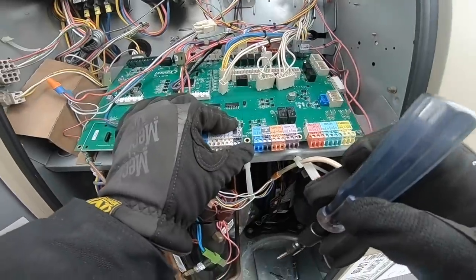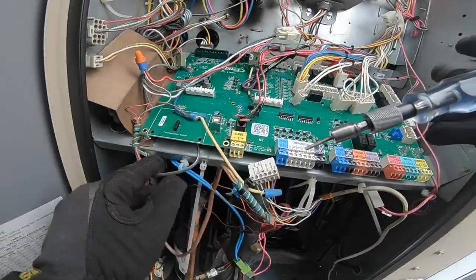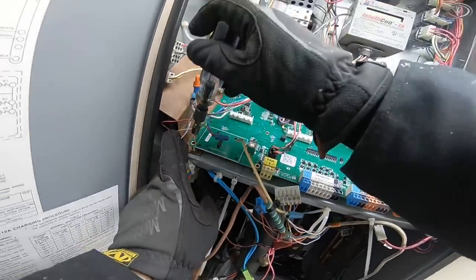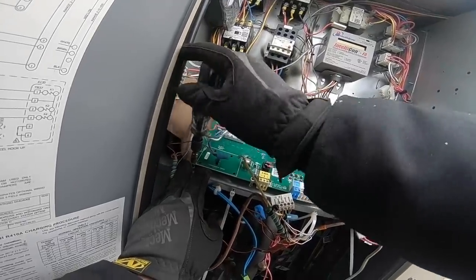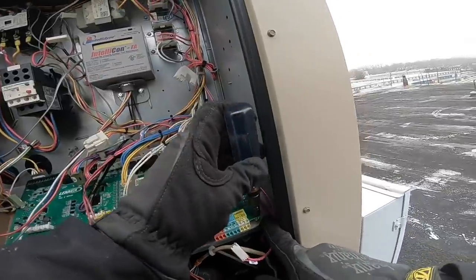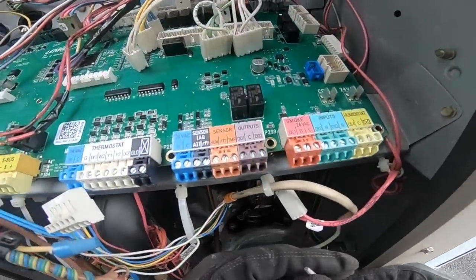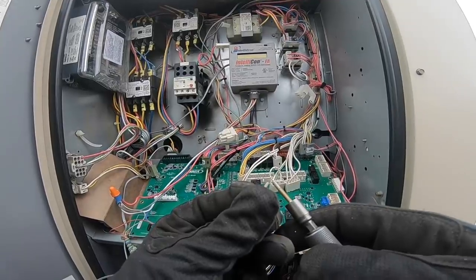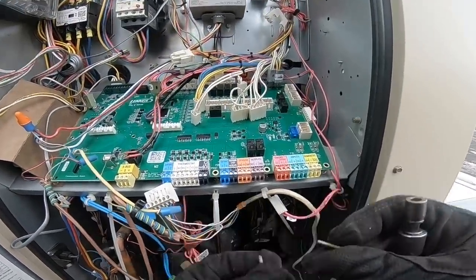The problem is when you got a chase like this, make sure nothing's underneath. I don't know why I see guys doing it sometimes, but they actually tuck wires under the board. Then what happens is the back of the solder pins might be a little sharp and they dig through the wires over time. At least that one's good. I do not like this connection. I have to dig through my truck because I shouldn't be able to pull them out. Like any of them are worn out.